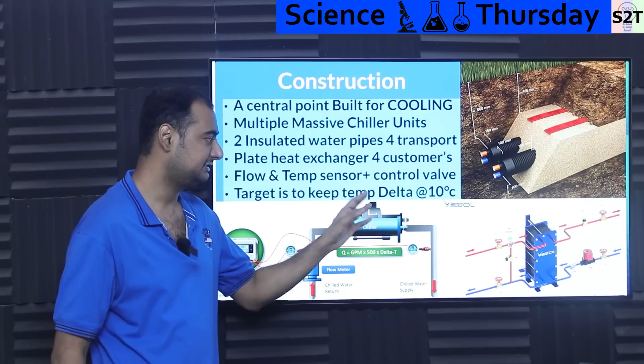The target is optimization at 10 degrees Celsius, but remember that 10 is flexible. If the system was designed for an 8 degree T delta, they'll focus on 8 degrees. If it's designed for 15 degree T delta, they'll focus on 15.